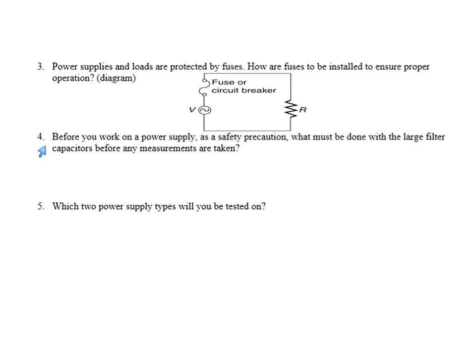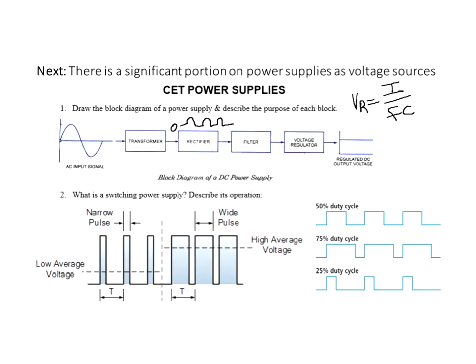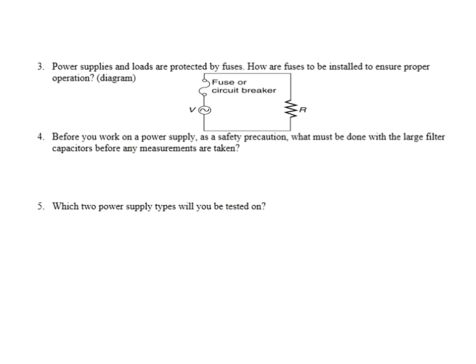Before you work on a power supply, when you look at the block diagram, you'll see large capacitors placed in parallel. These are generally really big: 25 microfarad, 1,000 microfarad, or even 2,000, 20,000, or 50,000 microfarad. You'd never see anything in the nanofarad or picofarad range. You'd need a lot of capacitance to actually filter in a power supply, especially with a very heavy or high current load.